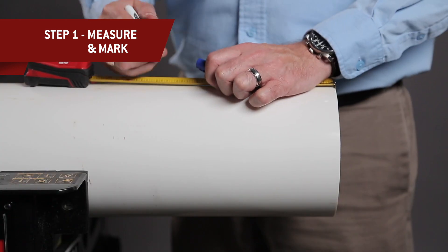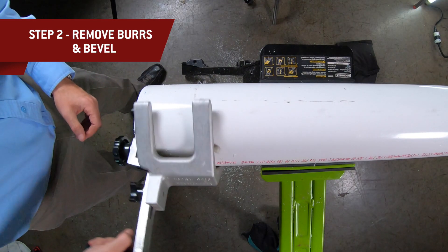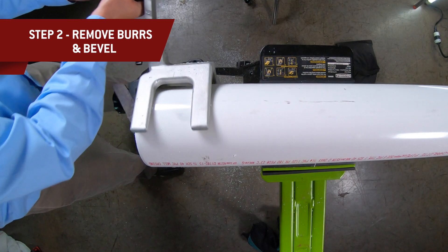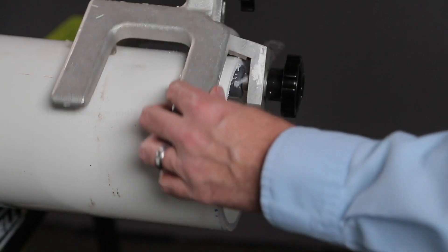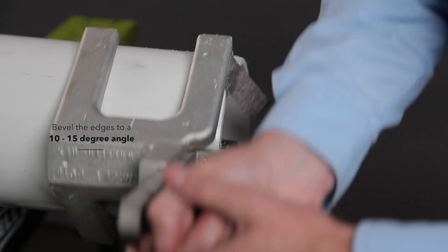Measure and mark the required length of pipe. Remove all burrs from the inside and the outside of the pipe with a deburring tool. Bevel the edges to a 10 to 15 degree angle.